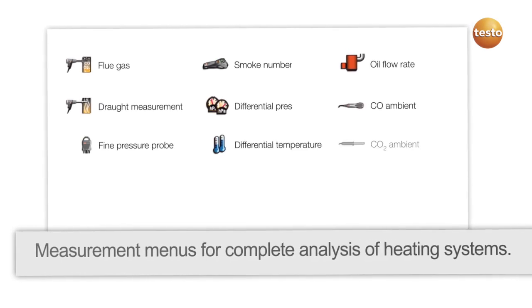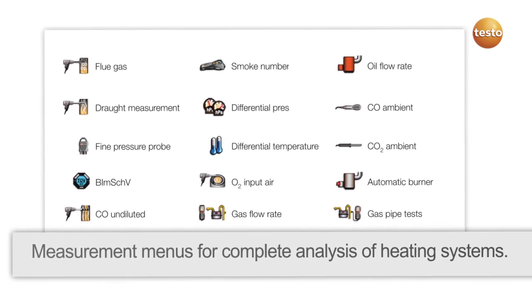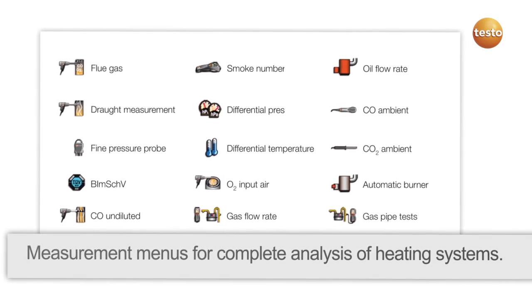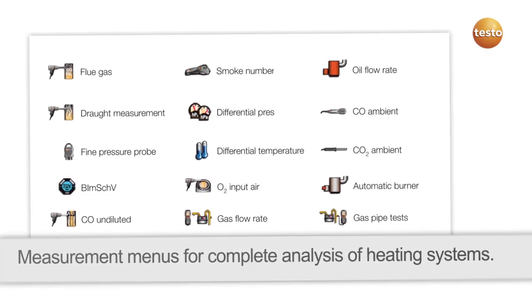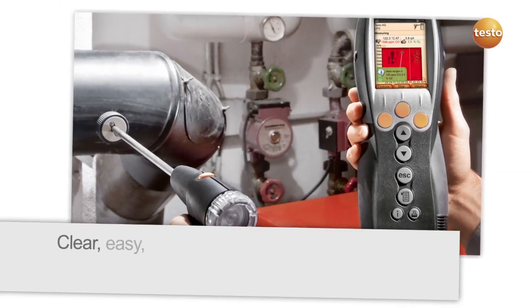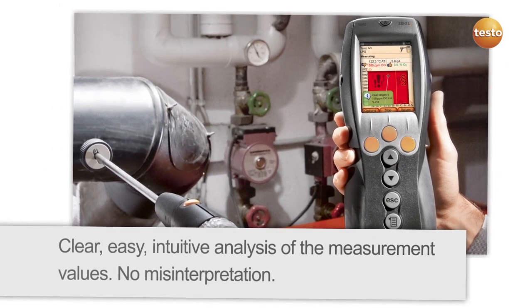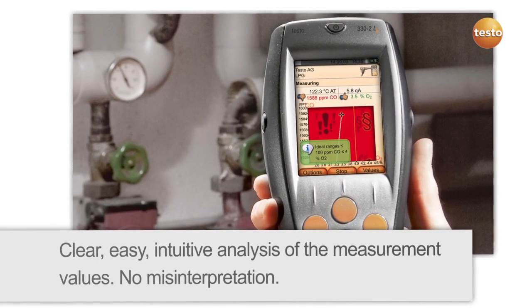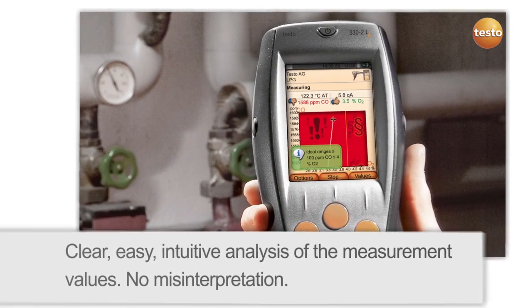The extended measurement menus allow a comprehensive analysis of the heating system, and the measurement data are clearly visualized on the display. This is shown by the following examples of typical measurement tasks. The CO concentration and the combustion shown here are poor. The Testo 330LL gives you the target values for the ideal combustion values.